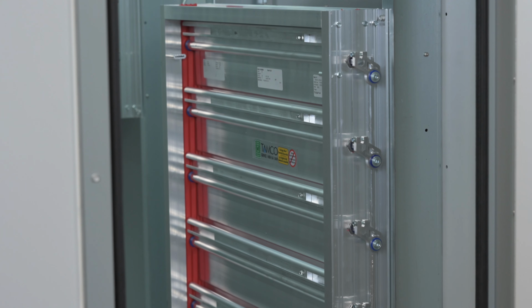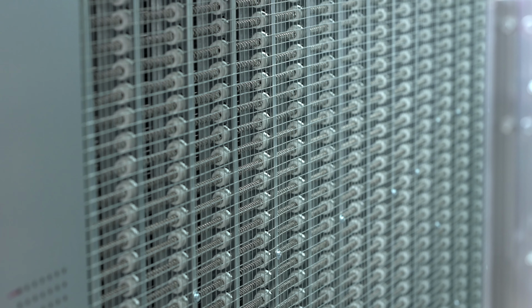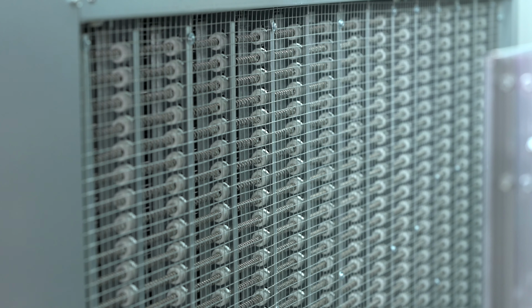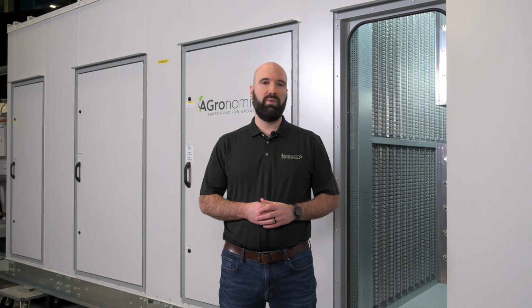In this second to last airflow compartment, you'll see behind me the 3 backdraft dampers, 1 for each fan. These dampers automatically close in the event of a fan failure, ensuring N+1 airflow redundancy. The other part of this section is the electric heater, and that electric heater is interlocked with the compressors to ensure that we're not taking an MCA MOP penalty to have it in there, but provides emergency heat if you ever need it. Generally speaking, the electric heater is only there if the facility is cold and dark for whatever reason, or suffers a power outage, or for first-time startup.